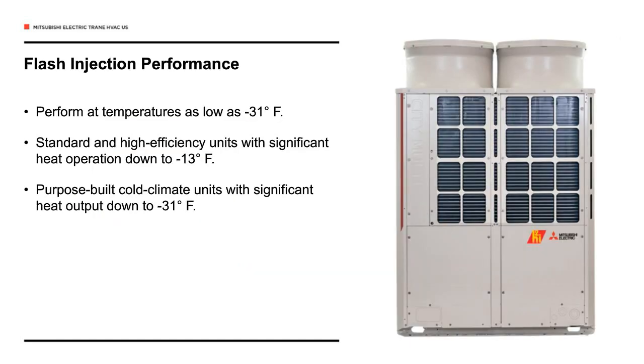If we look at performance, the Mitsubishi purpose-built piece of equipment that we have performs all the way down as low as 31 below 0 Fahrenheit. We rate that unit down to 22 degrees Fahrenheit below 0. The standard equipment, for the most part in the industry, manufacturers will rate to about 13 below 0 Fahrenheit. So you can see that this is not the technology from 20 or 25 years ago, where you had to turn it off at 25 degrees Fahrenheit. We're operating well below 0 with significant heat output at those lower temperatures.